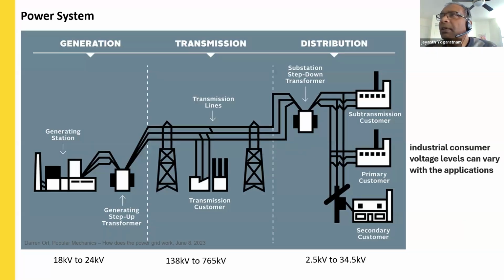So overall, when it comes to the power system, it can be divided into 3 sections: generation, transmission, and distribution. The power generation is done at 18 kV to 24 kV voltage level. This is the typical voltage generation used by the bulk generator systems in North America. When it comes to the transmission system, the voltage level will be stepped up to 138 kV to 765 kV using the transmission substation. And as we all know, this is being done in order to reduce the losses taking place during the transmission along the transmission line. At the same time, this will help us to reduce the cross-section of the conductors which are used to carry the power.